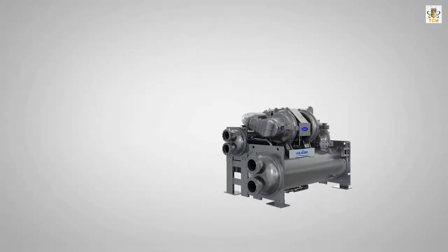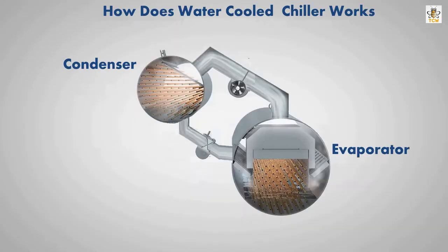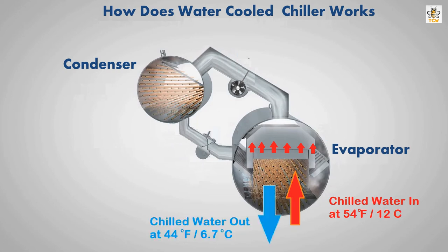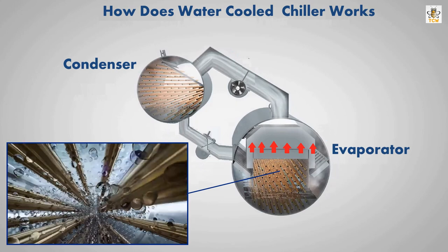The water-cooled chiller transfers heat from chilled water to condenser water as follows. The chilled water enters the evaporator tank at 54 degrees Fahrenheit or 12 degrees Celsius. Inside the tubes, chilled water releases its heat and the temperature drops, flowing out at 44 degrees Fahrenheit or 6.7 degrees Celsius. This heat is absorbed by refrigerant where the temperature is lower, causing the refrigerant to boil and evaporate.